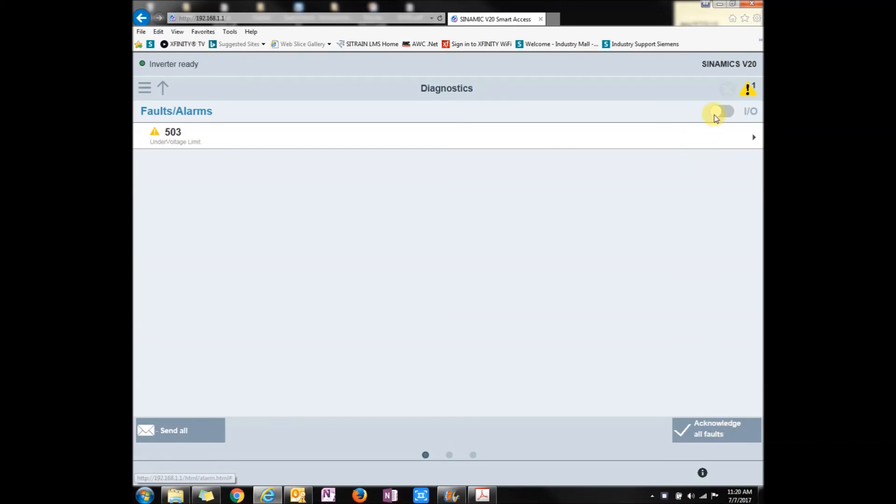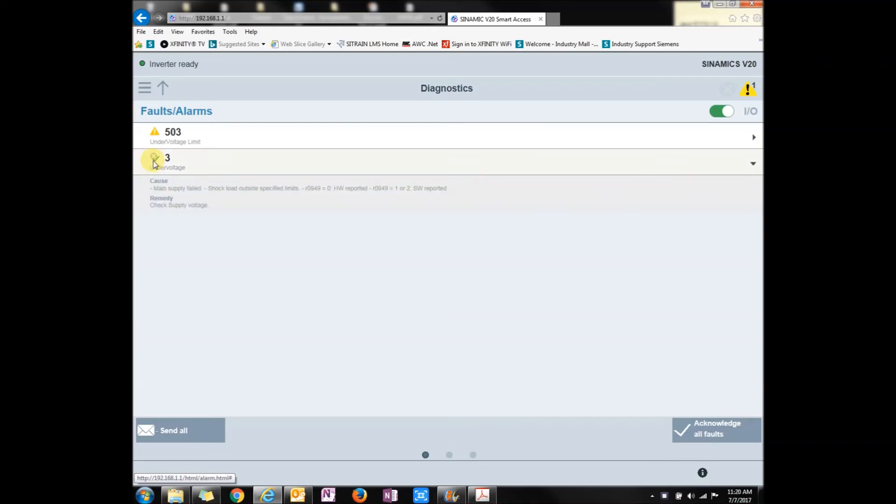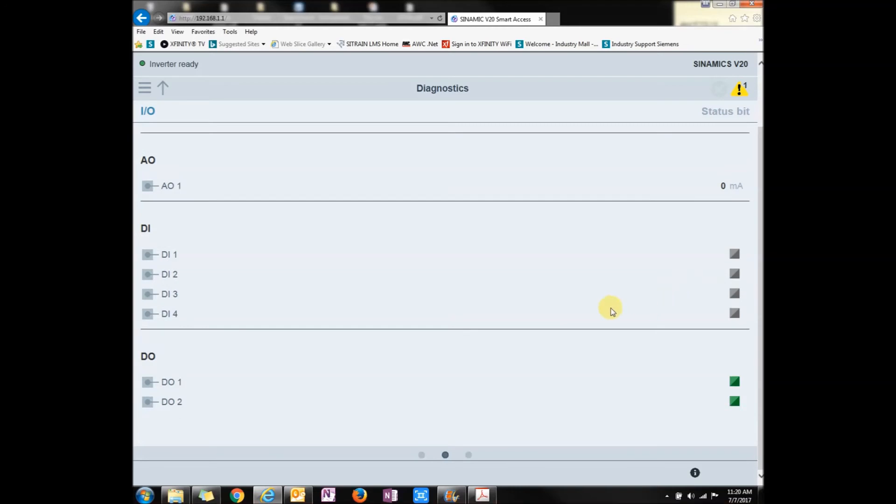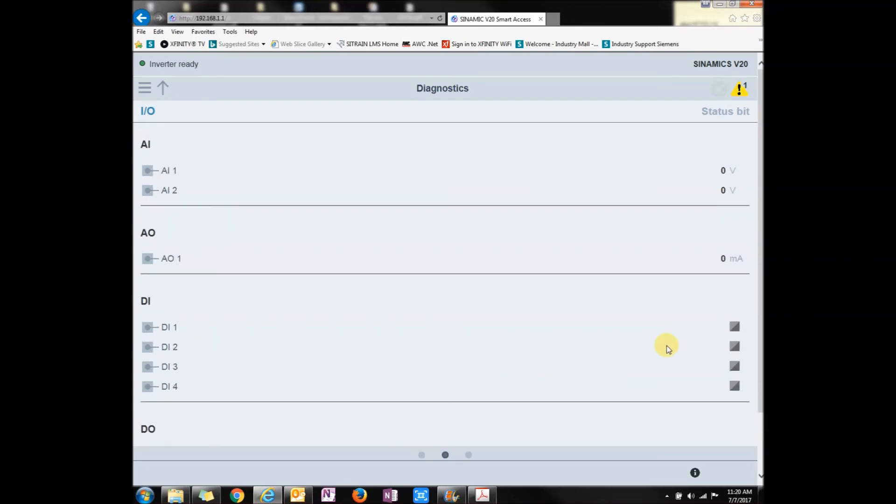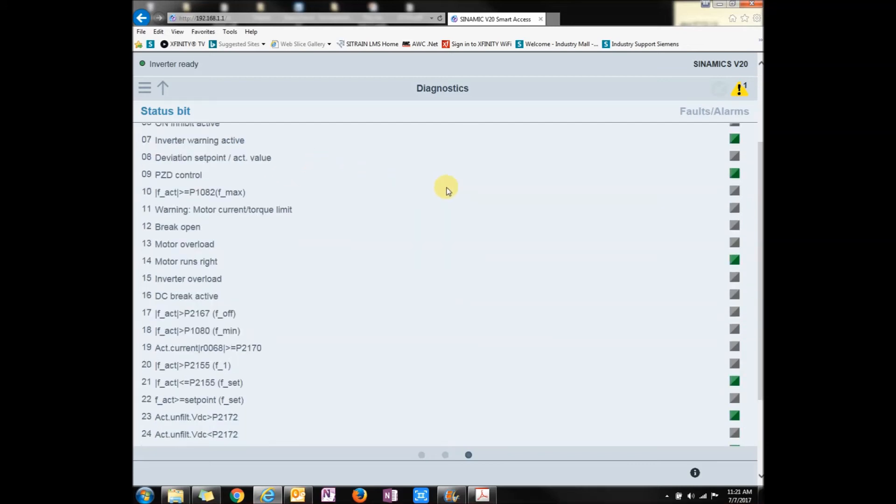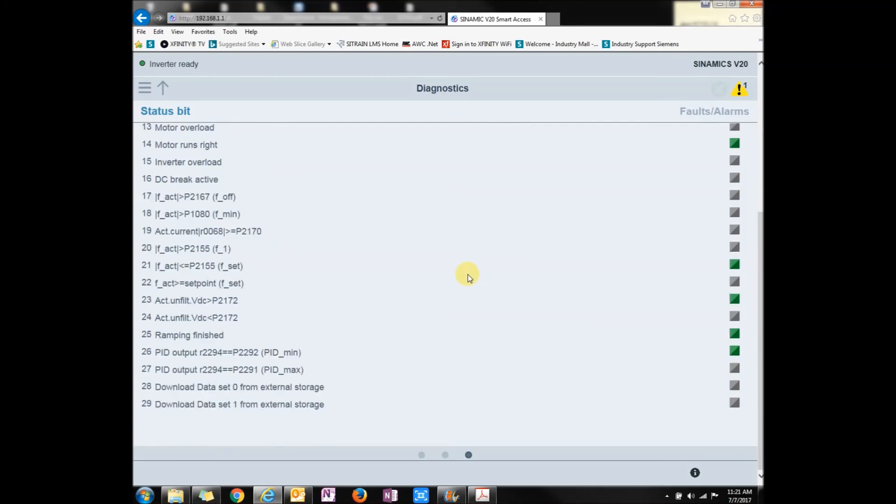There's the acknowledge fault, which will acknowledge any faults that are active that have been cleared. There's another thing you can do: you can click this little toggle button, which should show your past alarms that went on that you've already accepted. If you click on the second dot right here, it will bring you to your analog inputs, analog outputs, digital ins and digital outs, and it will show the status of what they are currently. Right now, my DOs are on because it's ready to run and not faulted. Click this third dot, which is your status bits for your Modbus communication and your USS communication. You can see every single bit. This is really good for when you're troubleshooting any USS protocol.